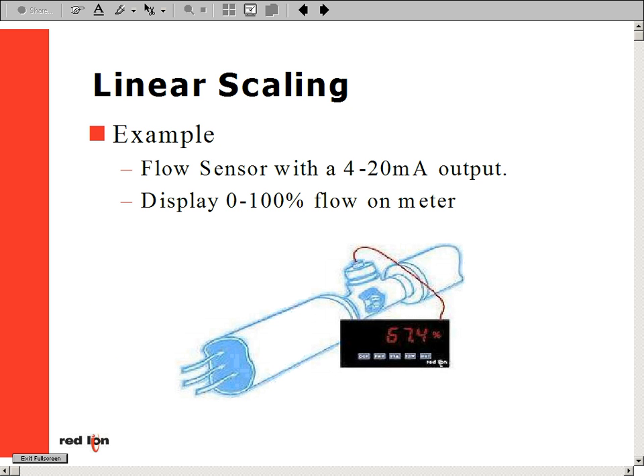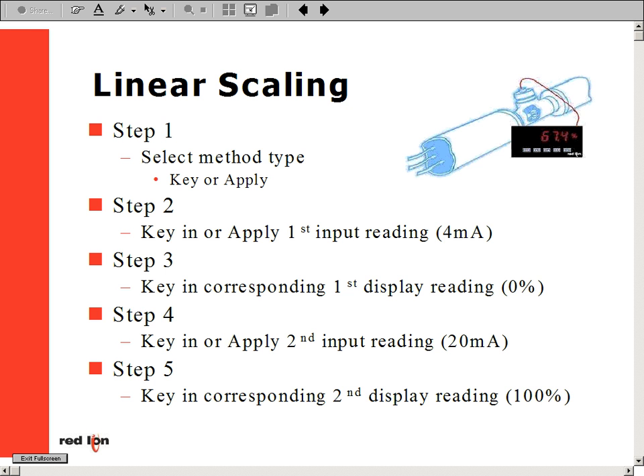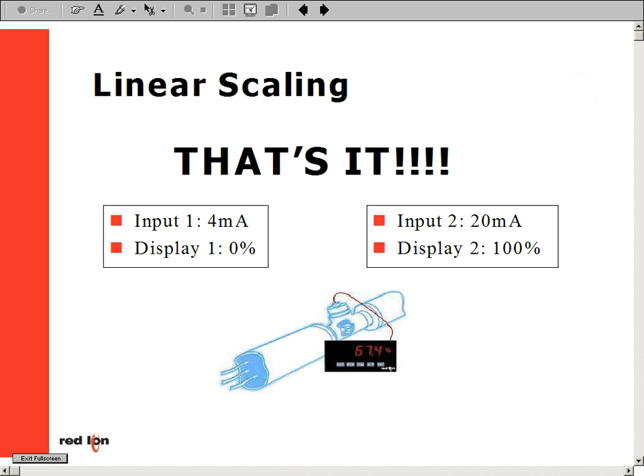The final step has us key in the appropriate display value corresponding to our high point. In our example, that is 100%. Scaling is now complete — no math calculations. All we need to perform linear scaling is four values: low and high input values, and low and high display values.